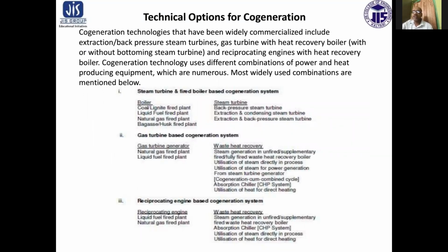Next are the technical options for cogeneration. Cogeneration technologies that have been widely commercialized include extraction back pressure steam turbine, gas turbine with heat recovery boiler, with or without bottoming steam turbine, and reciprocating engines with heat recovery boilers. Cogeneration technology uses different combinations of power and heat producing equipment, which are numerous. The most widely used combinations are mentioned below.